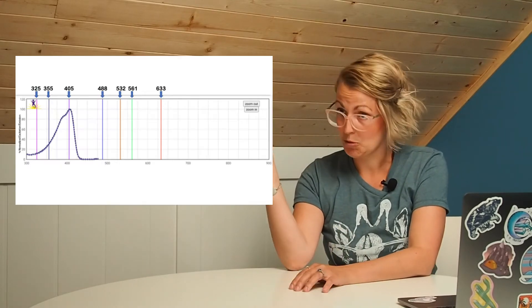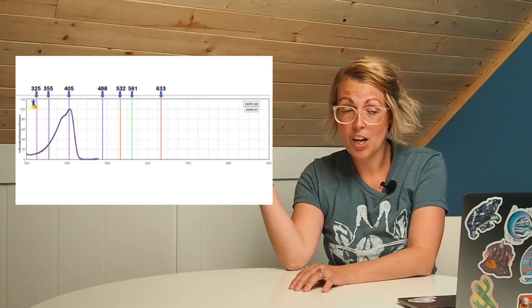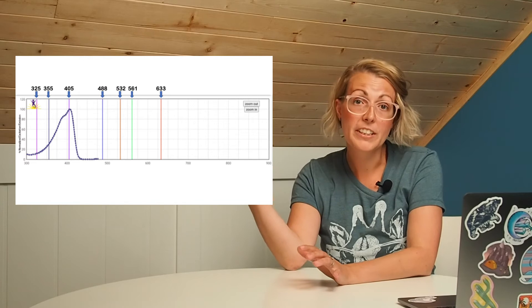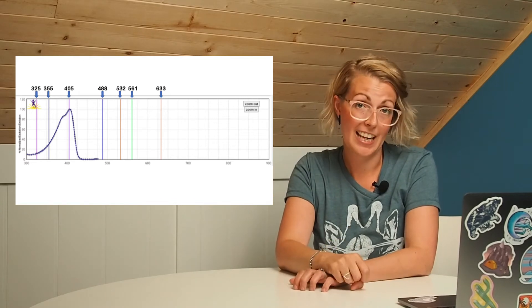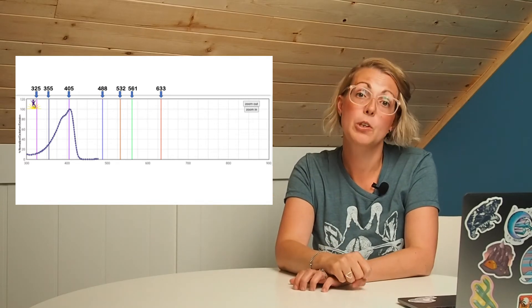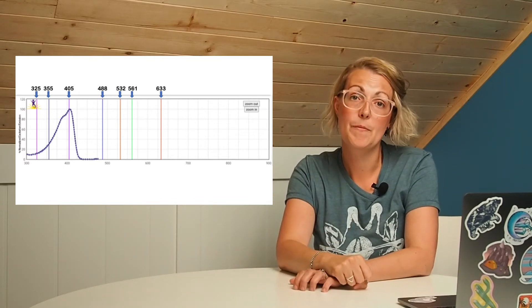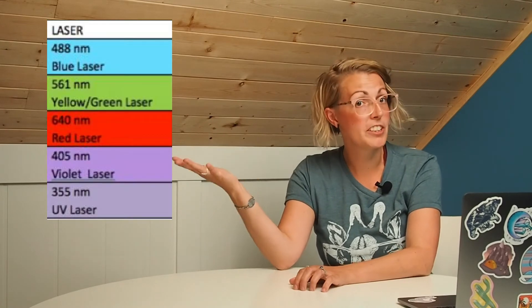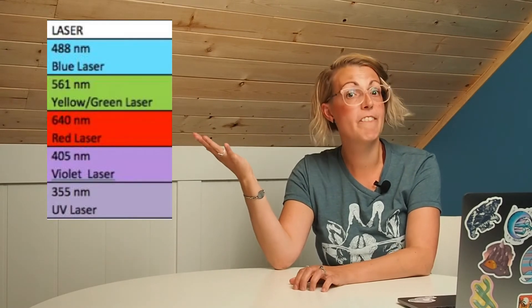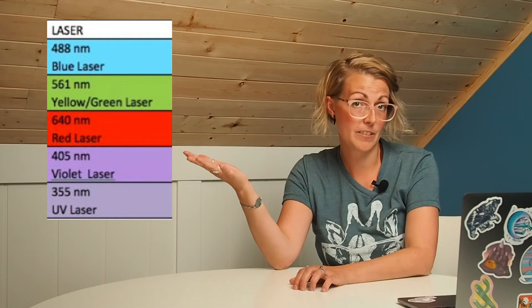When you're determining which lasers you can choose to excite this fluorochrome you want to make sure you pick one that is in that central peak zone of excitation. So if we look again at this representative plot which laser line would you choose to activate this fluorochrome? If you chose the 405 laser you are indeed correct. The peak excitation will come using a 405 laser. So if you wanted to use this fluorochrome you would need to first make sure that the instrument you're using had a 405 nanometer laser.